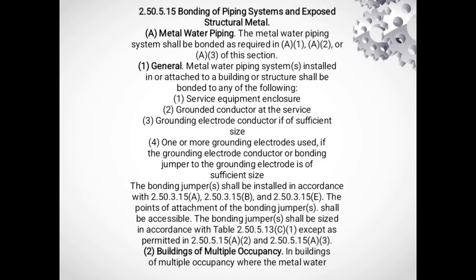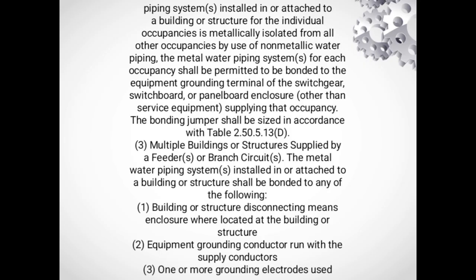In buildings of multiple occupancy where the metal water piping system is installed outside a raceway or enclosure, protection applies. Section 2.50.5.13A2 imposes a length restriction on external bonding jumpers. Section 2.50.5.13A3 mandates protection from physical damage. These requirements are designed to prevent damage to the bonding jumper which could compromise the integrity of the grounding system.